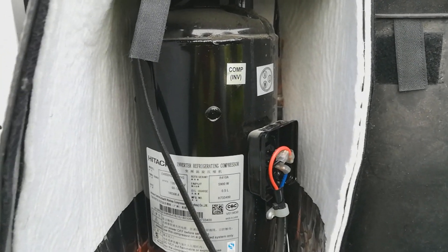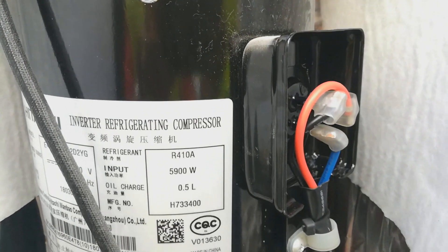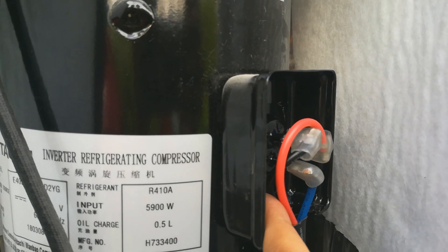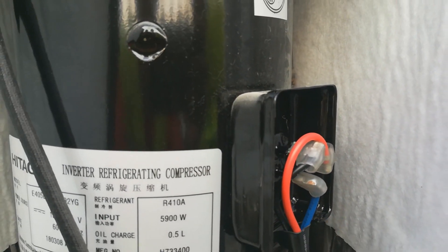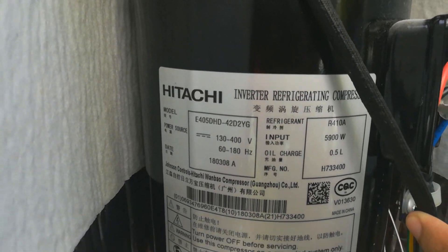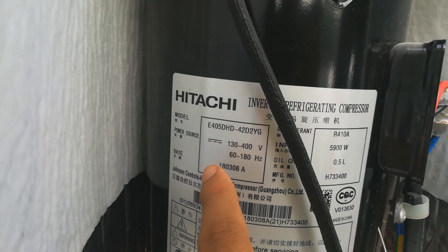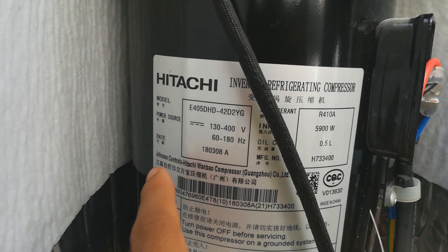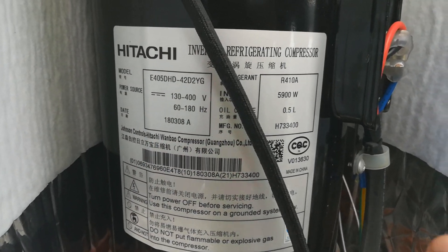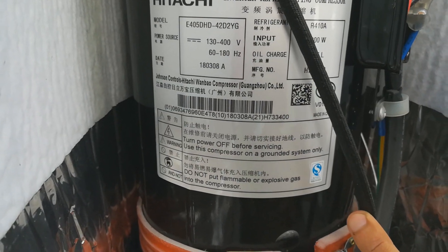Here is an inside look at the compressor. It uses an inverter compressor — specifically a Hitachi compressor. The power supply shown here comes from the board I showed earlier. The supply is adjustable, ranging from 130 volts to 400 volts, making it an adjustable speed compressor.